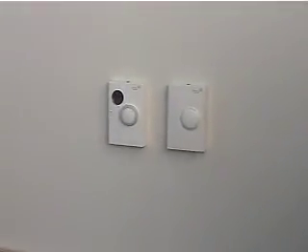We want to maintain no more than 800 parts per million of CO2, I believe. That will reset the ventilation minimum from all the way down to 0 up to a maximum setting of that VAV box. So that's the CO2 sensor. This right here is your thermostat, and I believe you have some questions on how that works.